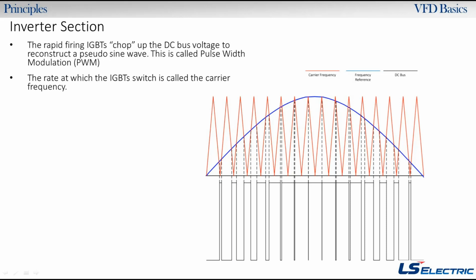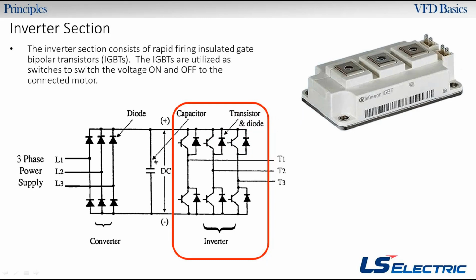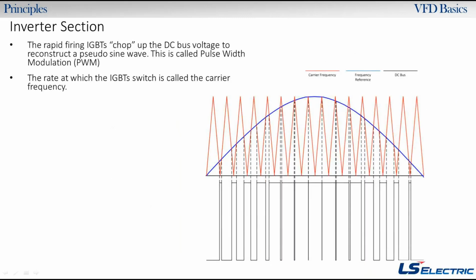If I go back a slide, you can see there are transistors on the positive side of the bus, which is this top rail, and then there are IGBTs on the negative side of the bus, which is this bottom one. Sometimes you'll be firing here, and sometimes you'll be firing here. You'll never have one firing here and there on the same phase at the same time, because that would make a direct short, and that would short out your DC bus. It's like a firing order on a car. Think of it like this is not a V8, it's a V6, right? Because there are 6 IGBTs on the output, you'll fire here, then here, then here, but you'll never have 2 in parallel firing at the same time. This is just showing, let's say, the positive side. So it's 0, 680 volts, 0, 680 volts, 0, 680 volts.